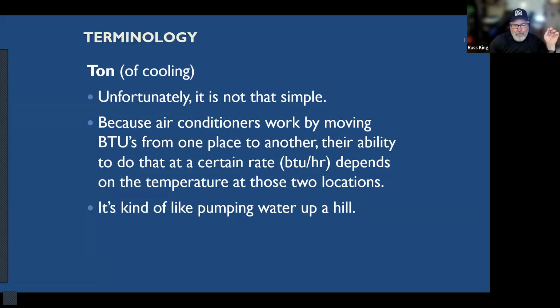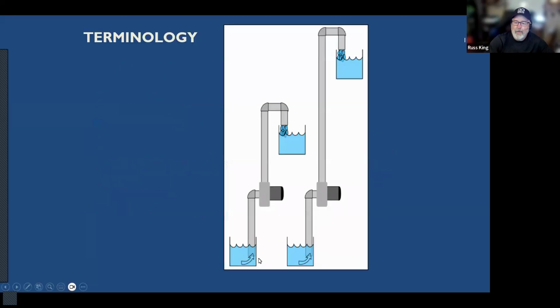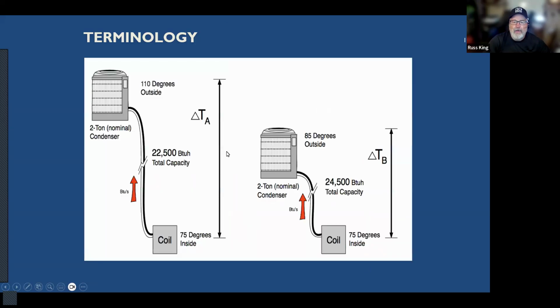Okay. And because air conditioners work by moving BTUs from one place to another, their capacity depends on where those BTUs start and where they end in terms of temperature. So it's kind of like pumping water up a hill. You can buy a pump that's rated at a certain gallons per minute. And if you're only going to pump 10 feet, you'll get a lot more than what it's rated at. But if you're going to pump it 100 feet up a hill, you're not going to get as much as what it's rated at. And heat pumps or air conditioners are kind of the same, and heat pumps too, for that matter. So, the same exact pump, if you're pumping it up a certain distance, you'll get more out of that same pump than if you're trying to pump it up much higher. Okay. And air conditioners are very much the same.